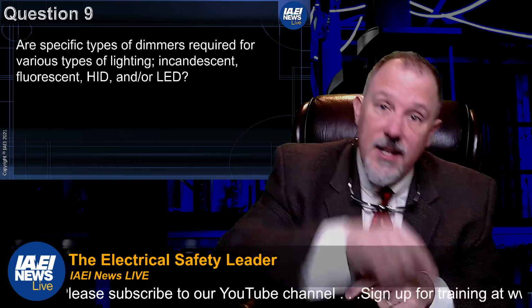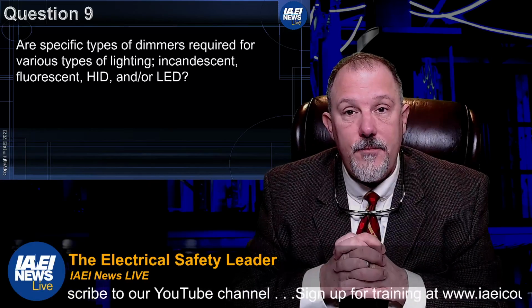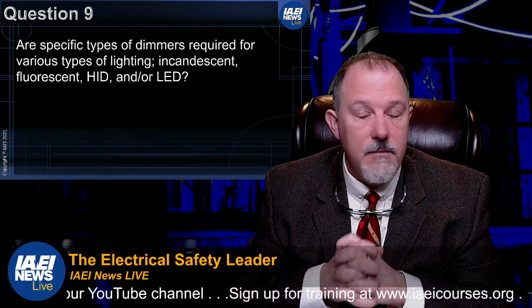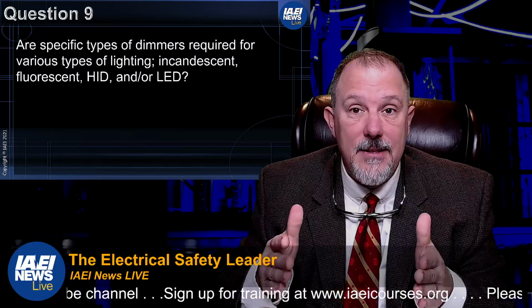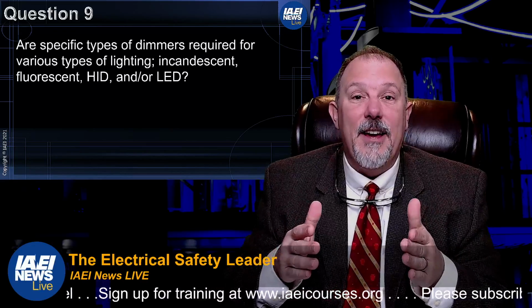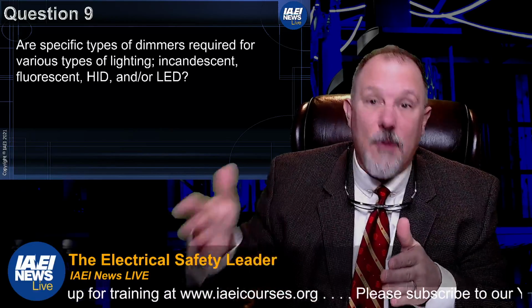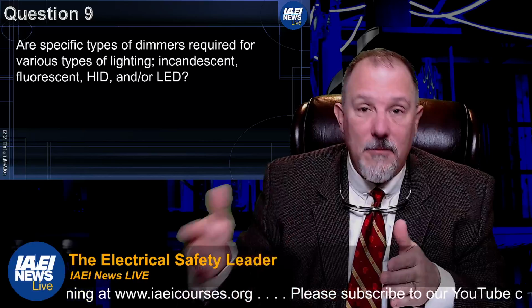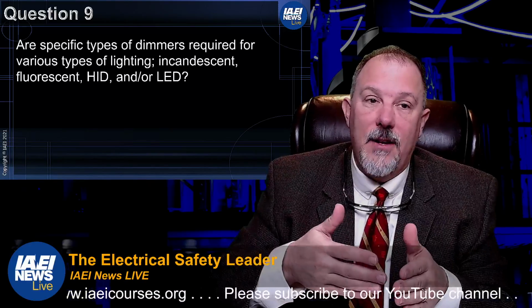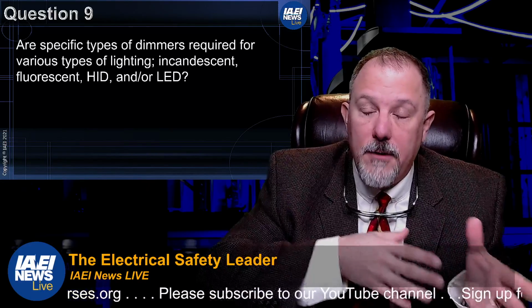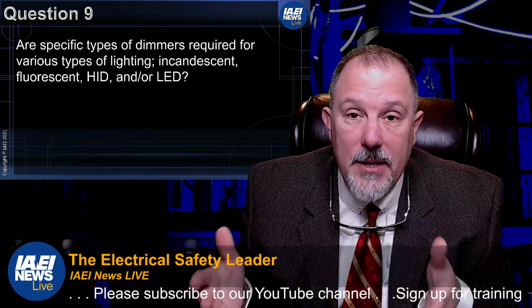We also just talked about the fact that LED drivers could have inrush currents that may impact the performance of the circuit breaker protecting that branch circuit.